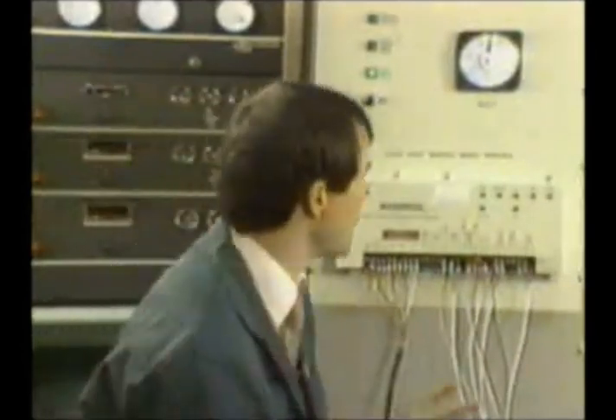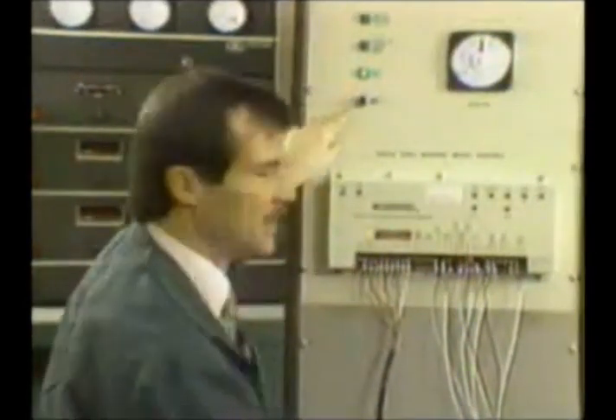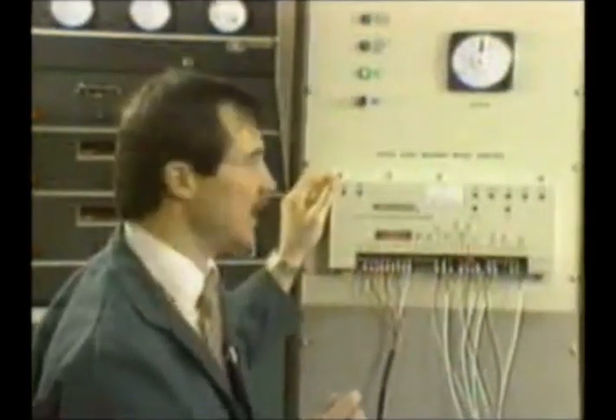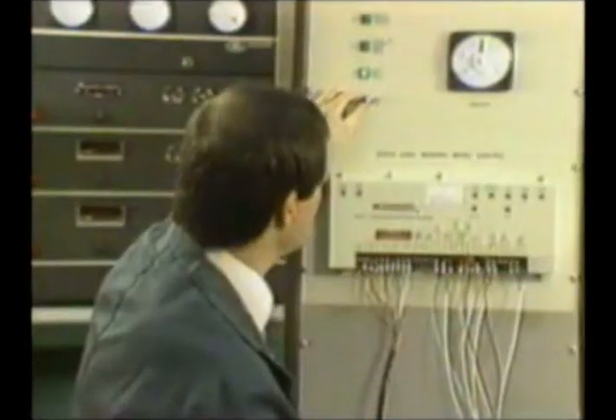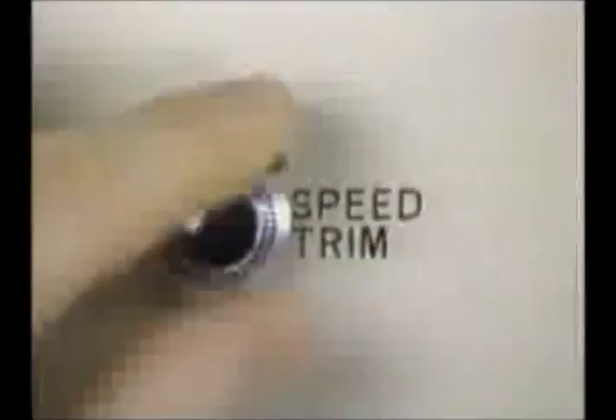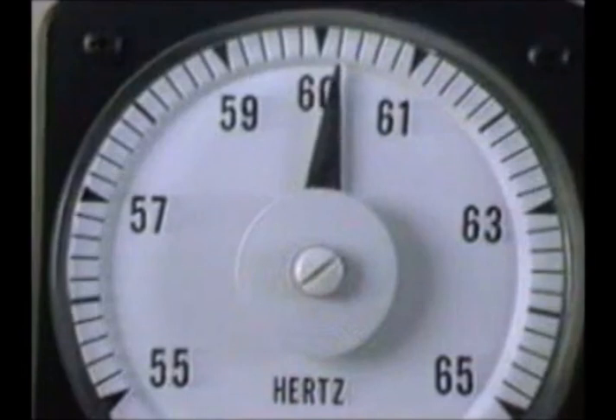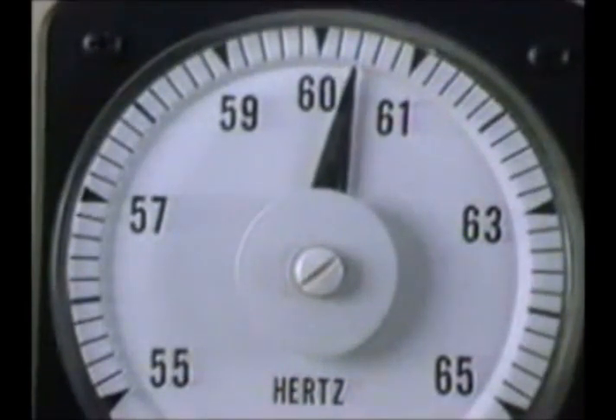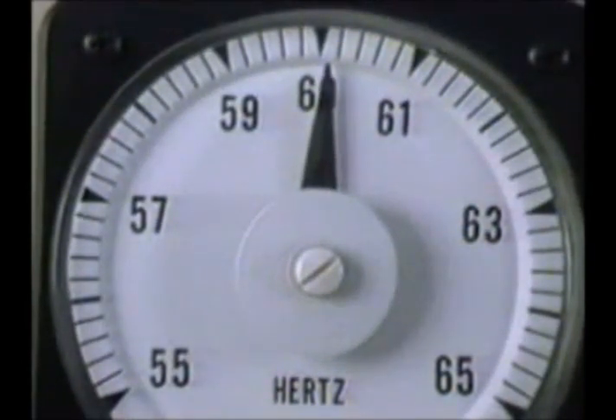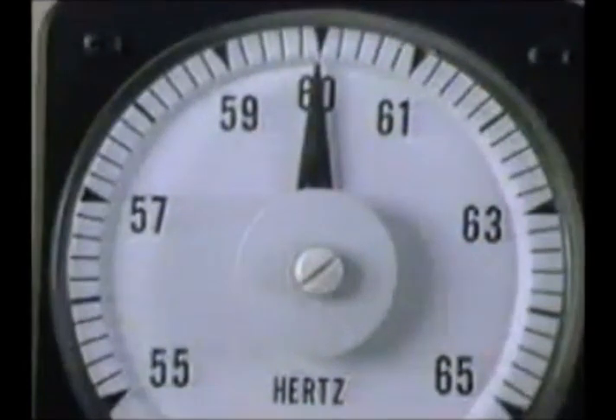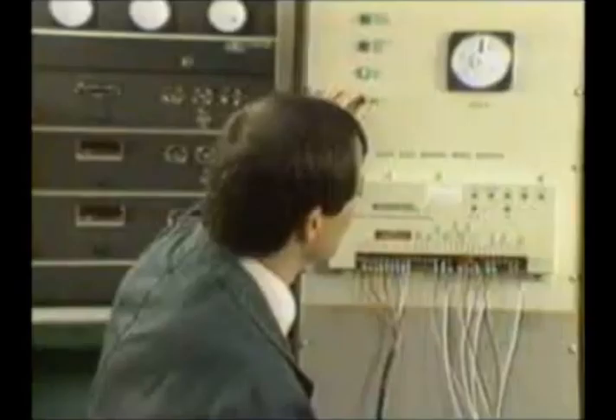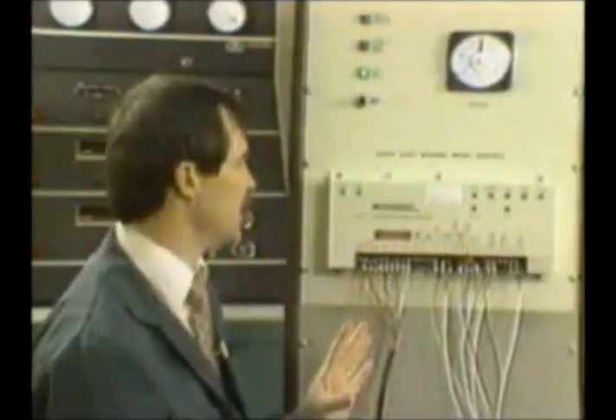Now, if you're not right at 60 Hertz at this point, you can use your speed trim potentiometer to go ahead and tweak in that speed. If I turn my potentiometer clockwise, I'm going to speed up. If I turn it counterclockwise, I'll slow down. So I'm going to set this so I read 60 Hertz exactly on my Hertz meter. That's where a speed trim pot can be used.